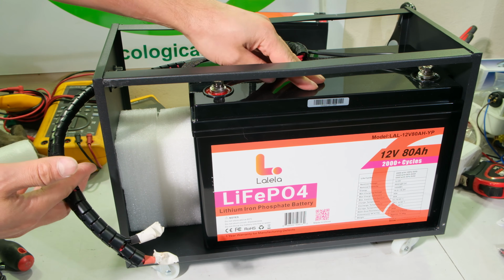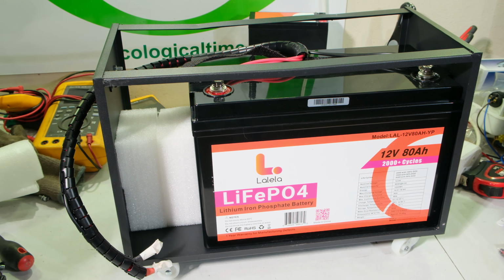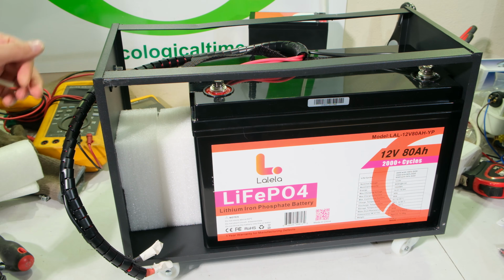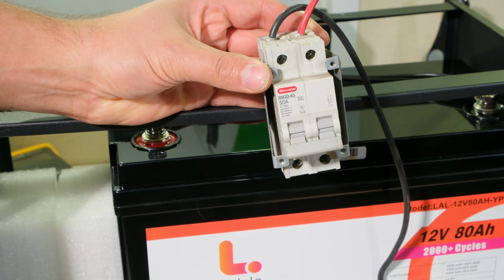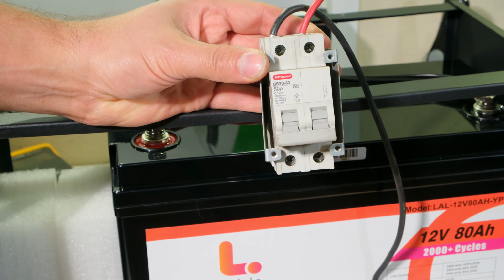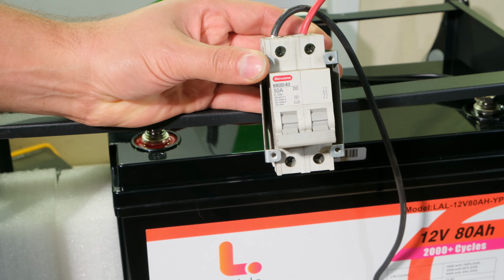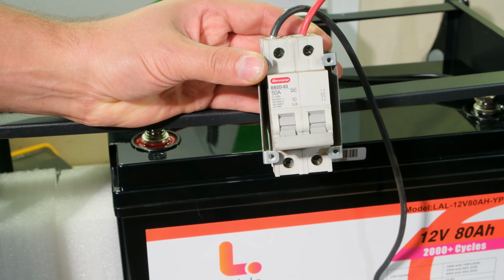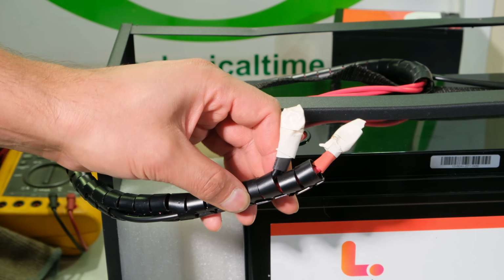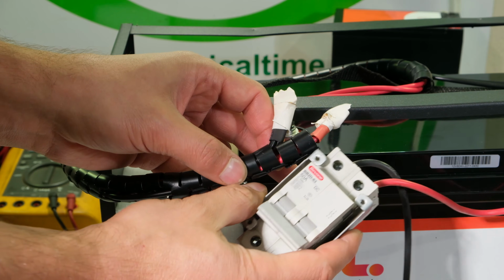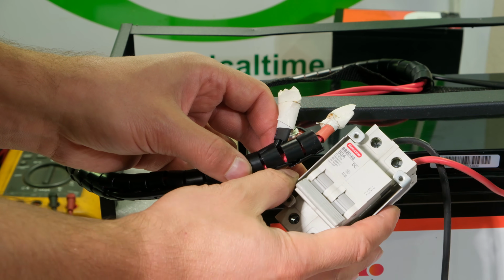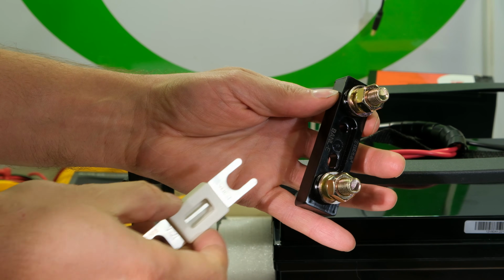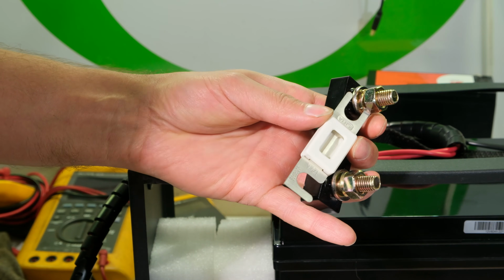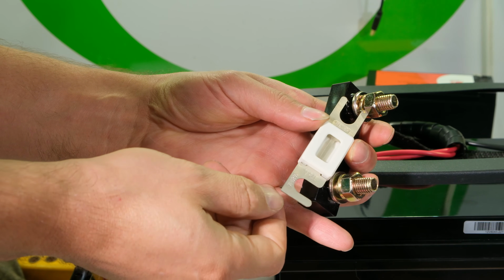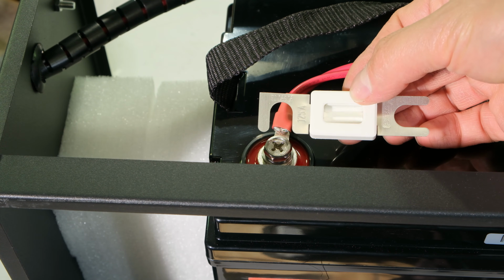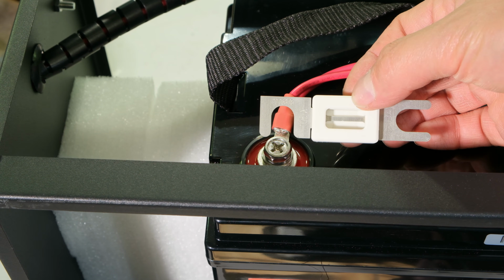We need some protection for this big battery, so I'm going to install some protection to make sure it's fine. Over here I have a DC circuit breaker. I'm going to cut the back of this little box and install it, so that if there's a short circuit anywhere after the battery, it will be protected by this overcurrent protection. Another option would be to install a fuse, with the fuse link installed right at the battery, for example right here, to make it safe.